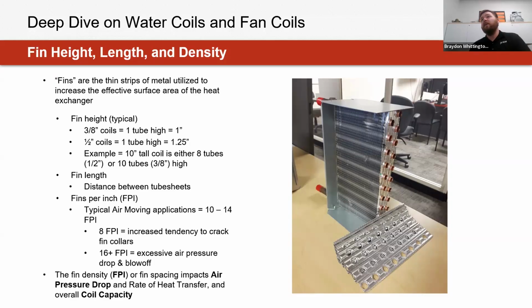Another common parameter that you would see when talking about fins, and commonly see listed in specifications, is fin density. So how many of those fins are within an inch of space for that coil? A higher fin density is effective as it's going to allow for more transfer of energy or a higher level of capacity. But one consideration is that as we increase the number of fins in succession on a coil, that also increases the resistance that coil adds to our system, or, when we're talking about fans, how much energy that fan needs to compensate for.